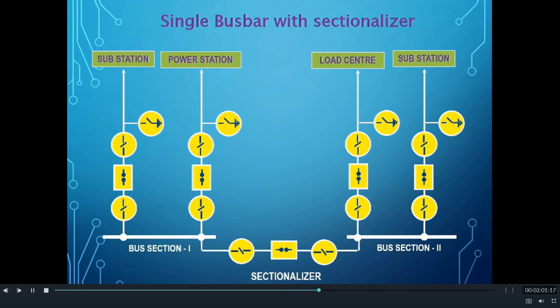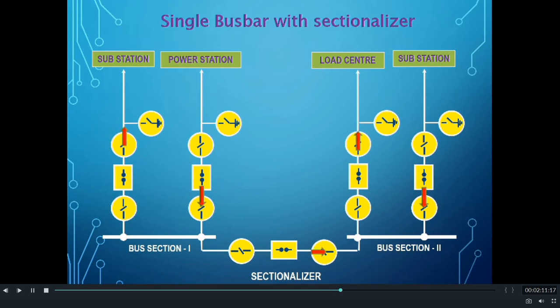That is, a Circuit Breaker with Isolators on both sides is also used as a Sectionalizer. These Sectionalizer circuit breakers are provided protection from relays.